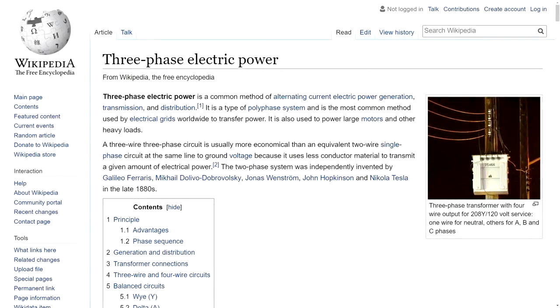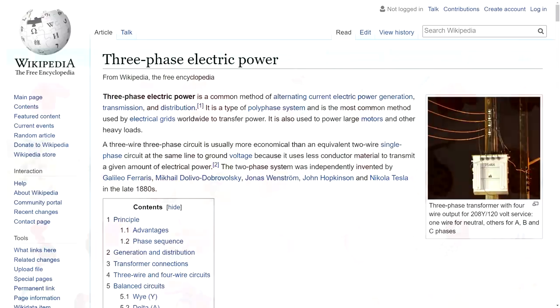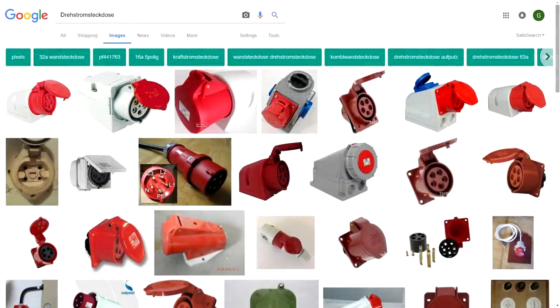Okay, so in order to understand how these components work together, we'll have to talk a little bit about the basics of three-phase power first. Now, three-phase power exists all over the world, is used in industries everywhere, but you won't necessarily find it in your average household in many countries. While in Germany, you actually do, as I mentioned before. So for example, if you have a three-phase outlet or socket in your garage or workshop, you will then typically find five distinct physical conductors in there: L1, L2, L3, the three phases, then N, the neutral conductor, and PE, the protective earth.